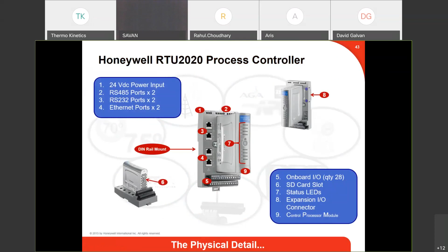The way it works is from my host system, from ControlEdge Builder software, I'm going to send to that RTU the firmware upgrade package. When the RTU receives that firmware upgrade package and confirms it has it in its possession, then on its own it'll go ahead and invoke the upgrade locally versus over the net. So that eliminates any suspect flaws in bricking of the RTU.